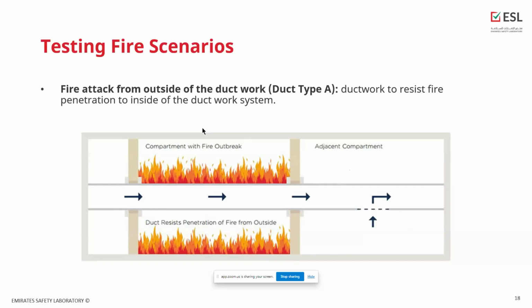Testing fire scenario, basically, because whoever is dealing with this system will be hearing a lot about duct type A, duct type B, or duct type C. So the basic idea is that it is the fire scenario. When the standard is trying to prove the applicability of the ductwork system, the test will just look at two fire scenarios: when the fire is generating with the duct having an opening or without the duct having an opening. So for fire attack from outside of the ductwork, we call it duct type A.